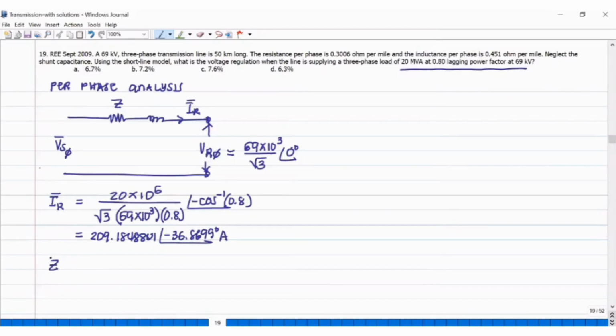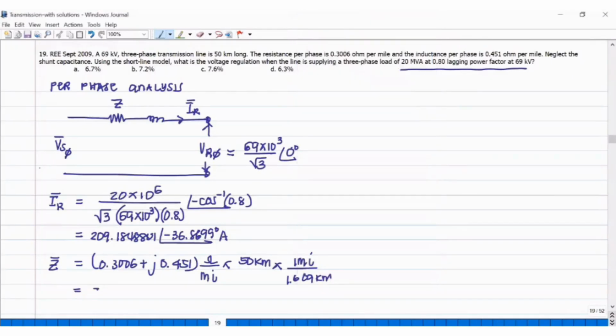We need the total impedance. That is 0.3006 plus j0.451, both in ohms per mile, multiplied by 50 kilometers, times 1 mile is 1.609 kilometers. So, the total impedance is 0.3006 plus 0.451j times 50 divided by 1.609, so 9.3412 plus j14.0149 ohms.